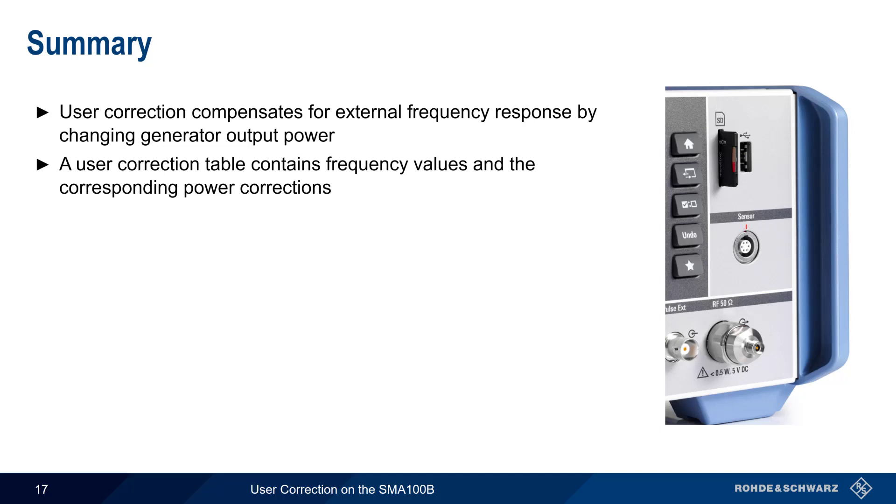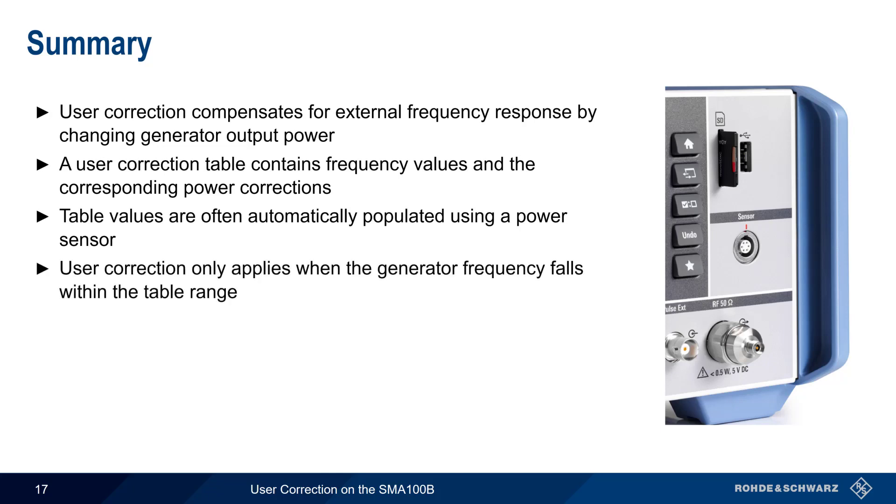Although these tables can be created manually, they are most often automatically populated using a power sensor connected to the SMA. It's important to keep in mind that user correction values will only be applied if the current generator frequency falls within the range of values in the table.